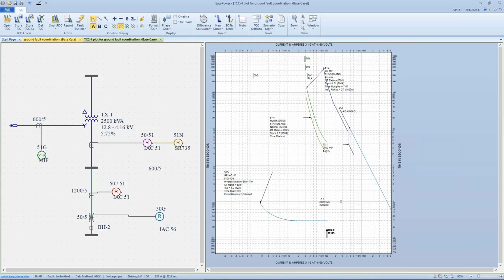And if we want to determine the time difference between a particular ground fault, we would select the two curves, see the difference calculator, and this shows us our time difference, in this case a little over 2 seconds at the closest point of approach.